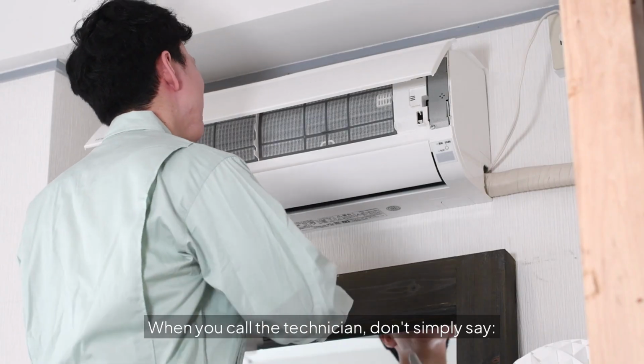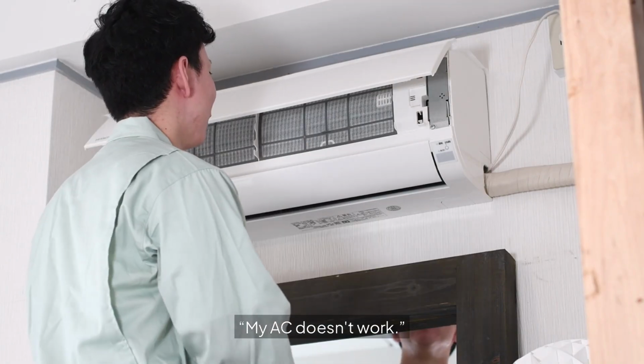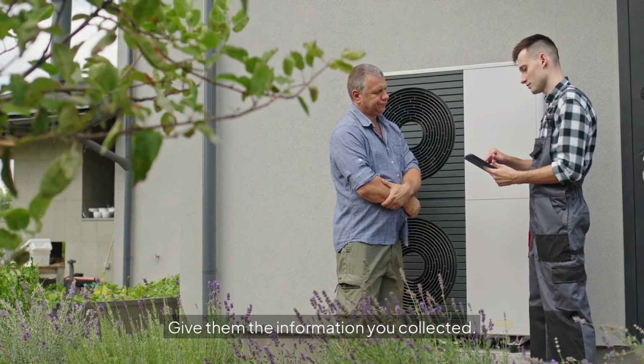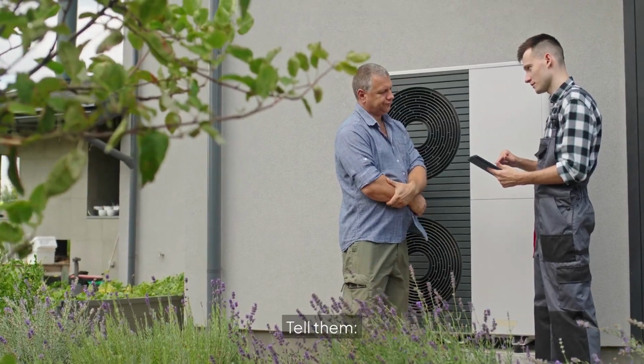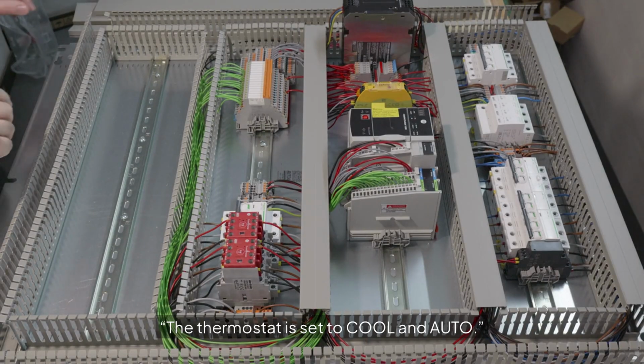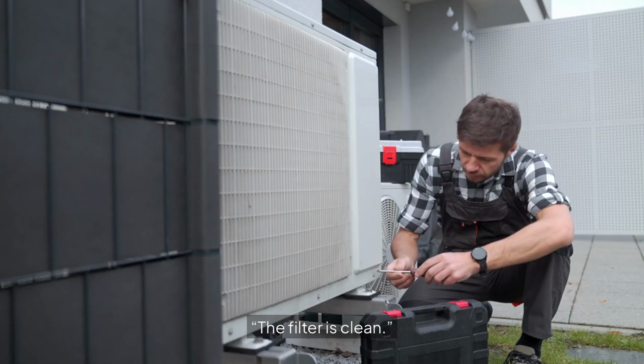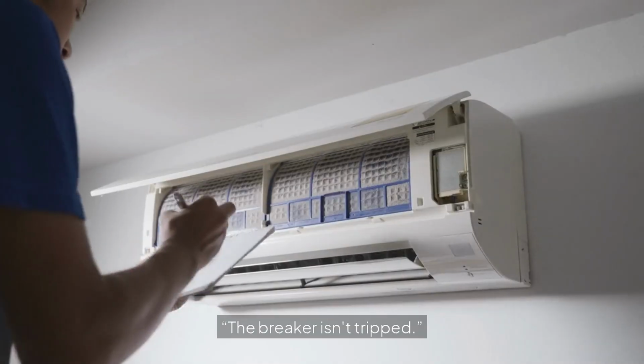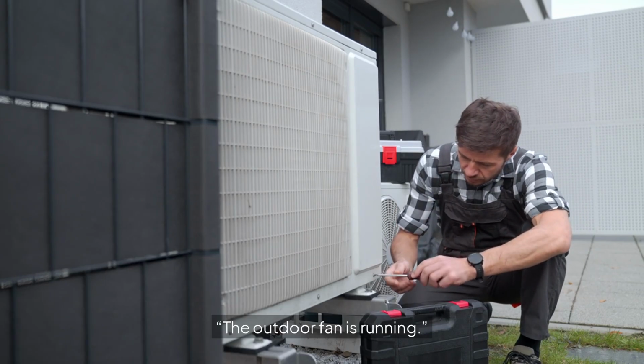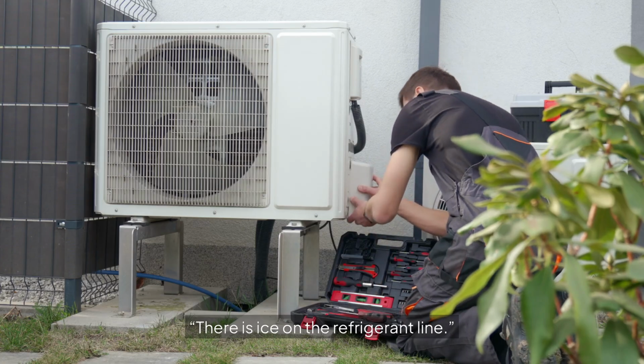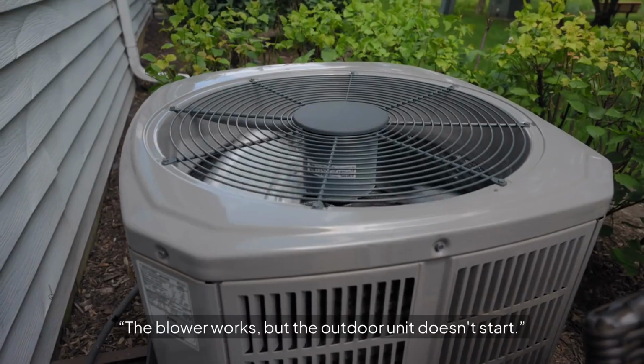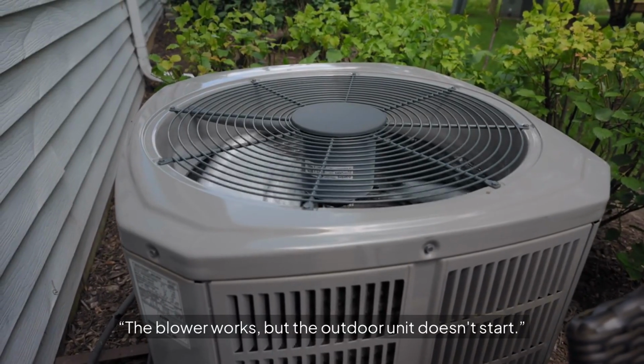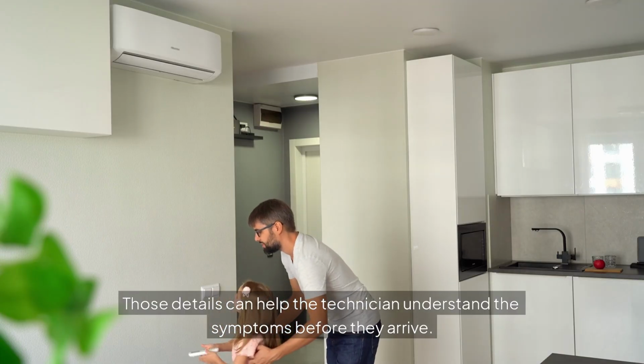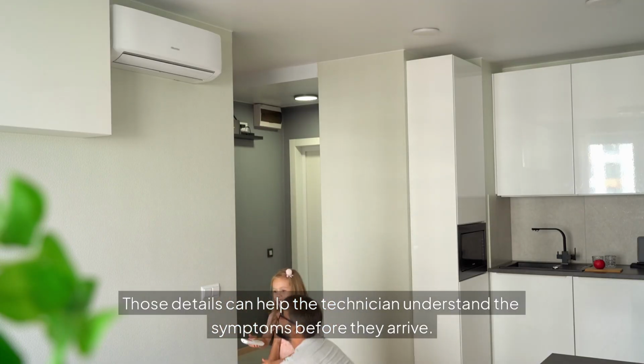When you call the technician, don't simply say, "My AC doesn't work." Give them the information you collected. Tell them the thermostat is set to cool and auto. The filter is clean. The breaker isn't tripped. The outdoor fan is running. There is ice on the refrigerant line. Or, the blower works but the outdoor unit doesn't start. Those details can help the technician understand the symptoms before they arrive.